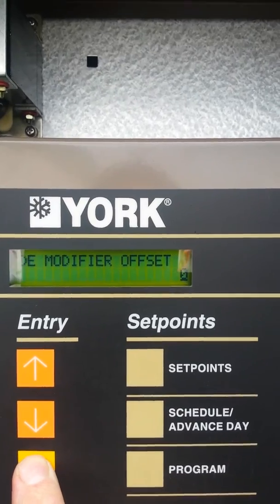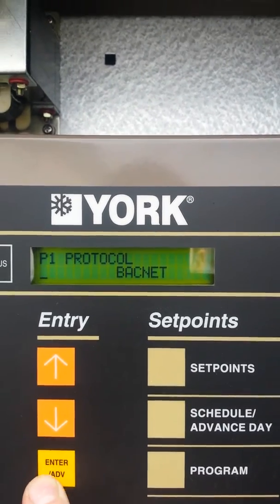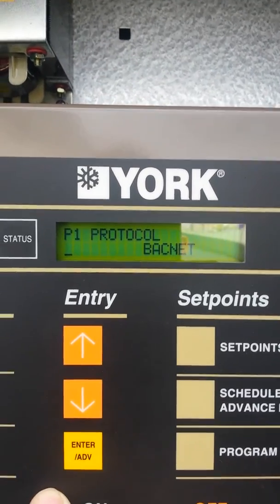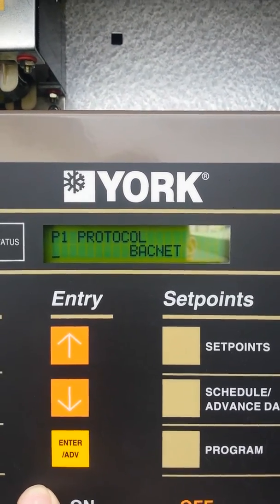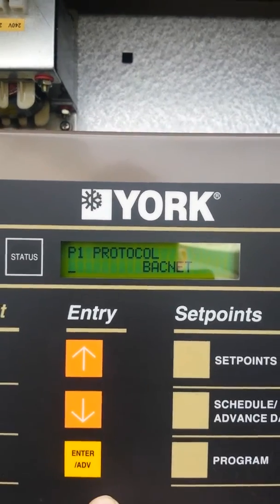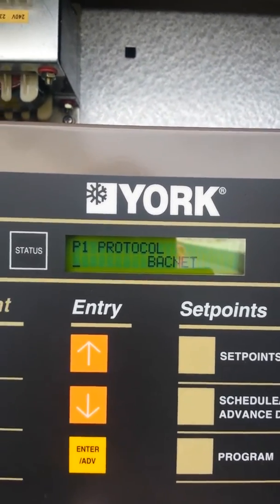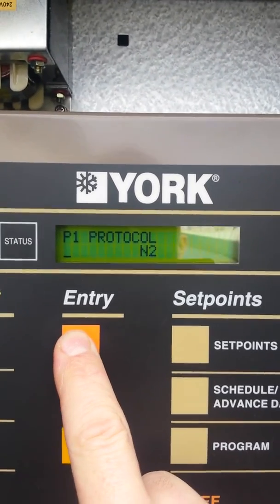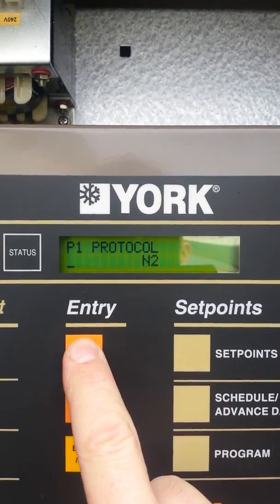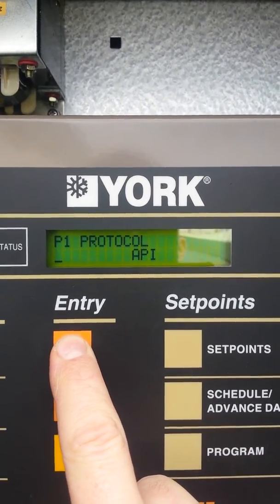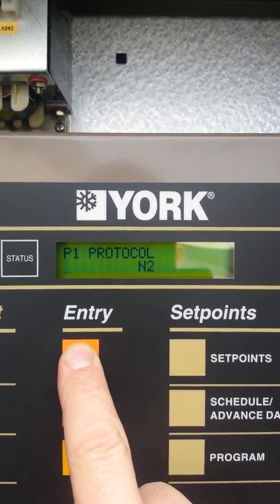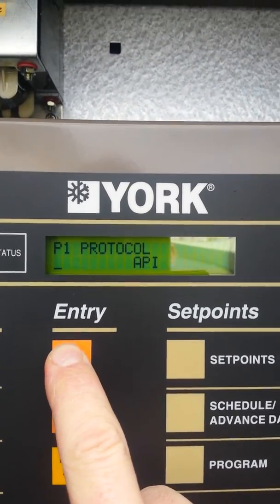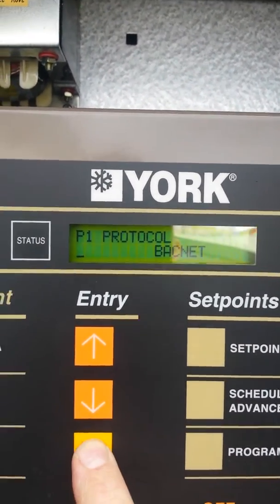You can change values by pressing the enter button and moving along. You come to P1 — this is very important. Right now we're setting up the P1 protocol, which is the BACnet protocol. There are two stages to the controls: P1 and P2 — I'll get to that in a bit. From here you can change to different things like N2 (the old York talk), API printer port, or back to BACnet. But today we're just going to stick with BACnet.